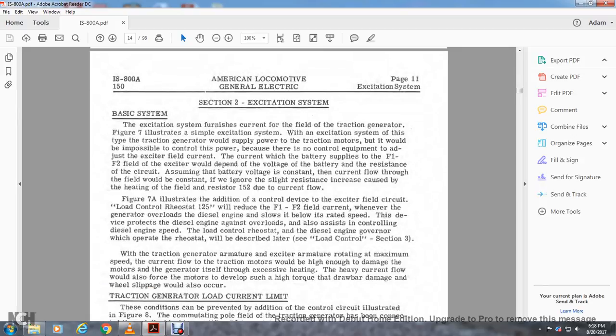Figure 7A illustrates the additional control device: the exciter field circuit with load control. Rheostat 125 reduces field 1 and field 2 current whenever the generator is overloaded and the diesel engine slows below rated speed, protecting the diesel engine against overload. The rheostat is also used for controlling the diesel engine load. The load control rheostat and diesel engine governor operation are described later in load control section 3.